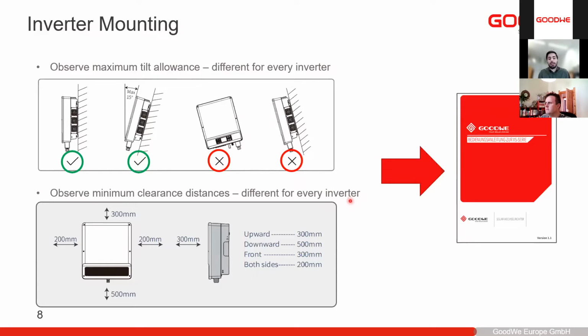In the manual, you also find the instructions for mounting and how to install the inverter on the wall. It's very important that you follow these instructions because this also affects the operation of the inverter and the heat dissipation. Make sure to always install it in the right way, so not upside down or on the side or anything. If you want to tilt it, the maximum tilt allowance is specified in the manual. Usually for most inverters, it's 15 degrees backwards. Also, please observe the maximum or minimum clearance distances to the sides, underneath, and also to the top. This is also used for maintenance and to make sure that the air can flow properly around it.